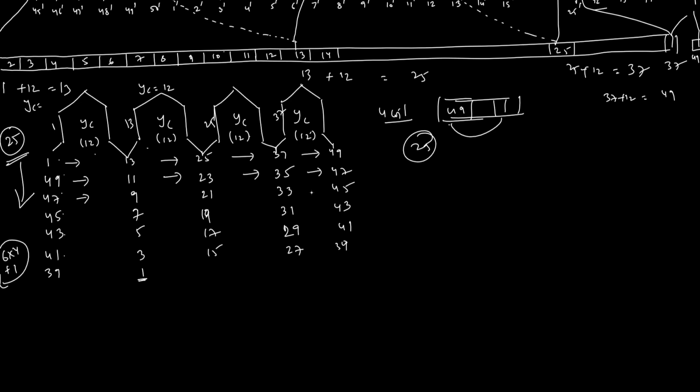Okay, so this is one coil, this is one coil, this is one coil, and this is one coil. 4 coils in one wave. So one more 4 coils, 4 coils, 4 coils, and this is also 4 coils. Up to here we have 6 into 4, that is 24 coils, and this is one more coil. So altogether I have 25 coils in one circuitry, starting from 1, again ending at 1.